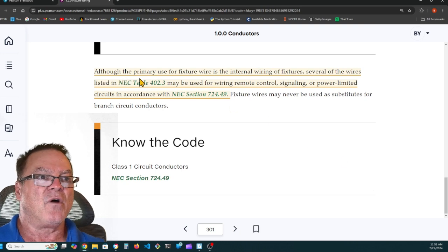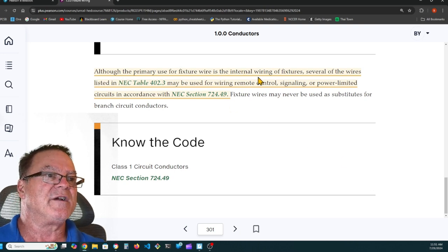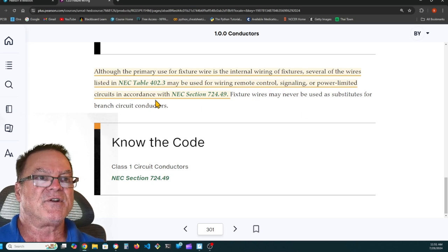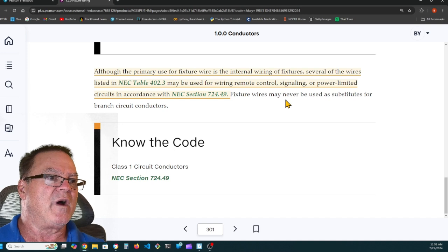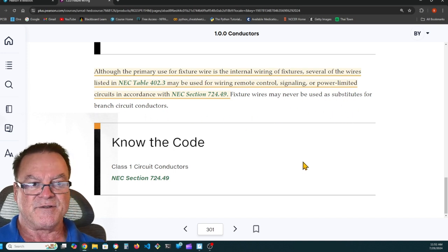Here's a highlight. It says, although the primary use for fixture wire is the internal wiring of fixtures, several of the wires listed in table 402.3 may be used for wiring remote control, signaling, or power limited circuits in accordance with NEC section 724.49. Fixture wires may never be used as a substitute for branch circuit conductors.